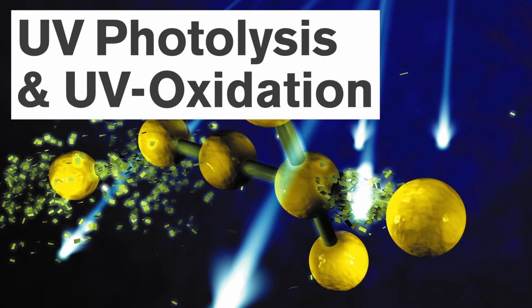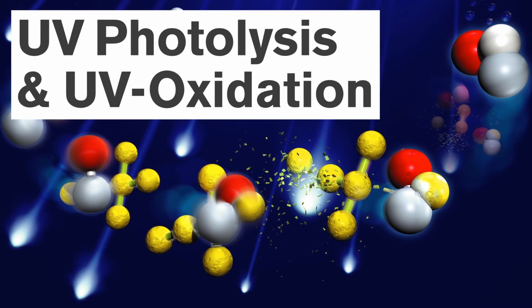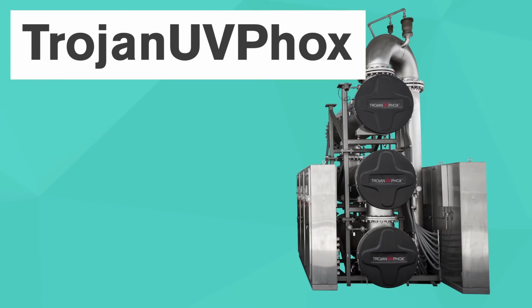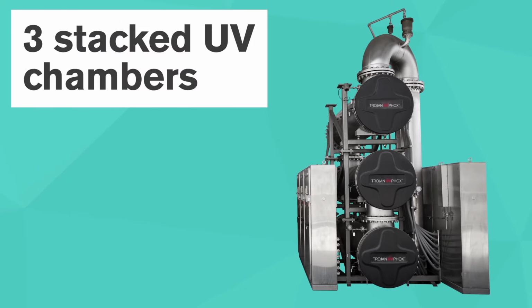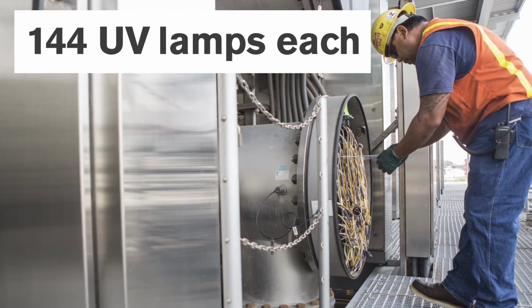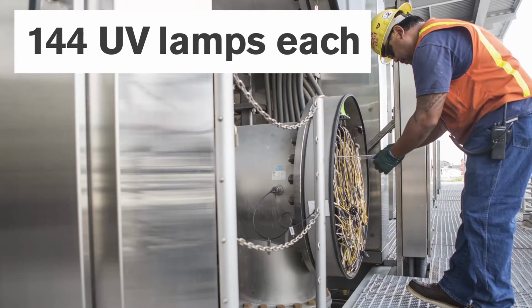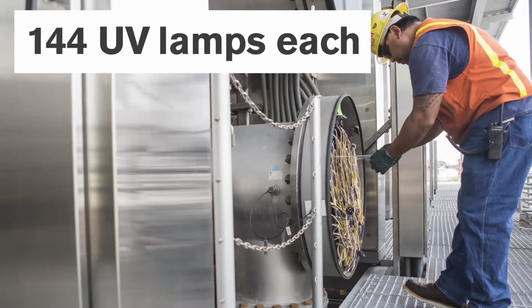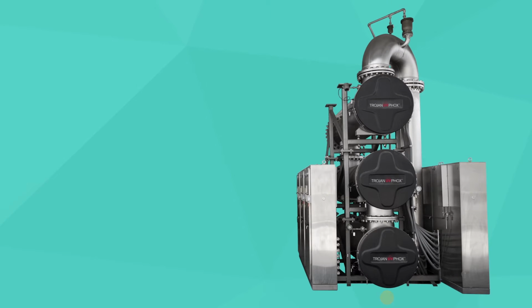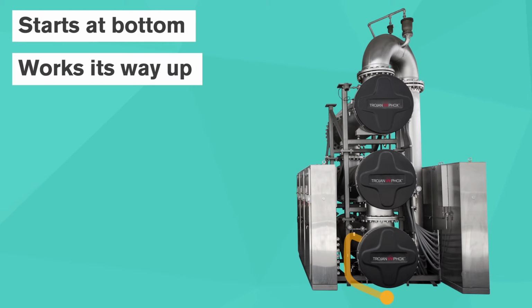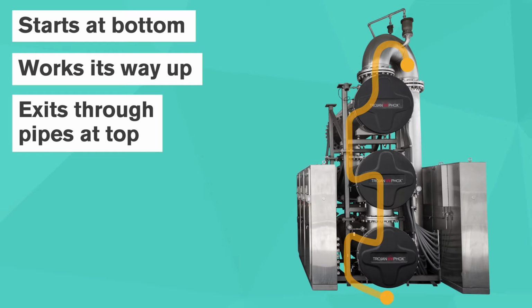These objectives are achieved using a dual process of UV photolysis and UV oxidation that takes place within TrojanUVPhox reactors. What you are looking at is a network of piped trains where 3 UV chambers are stacked in each train. Within each UV chamber, you will find 144 ultraviolet lights. UV lights look like a tanning bed lamp, but they are much more intense. Water flows into the bottom chambers, then works its way up through each set of lamps and finally exits outlet pipes at the top of the structure.